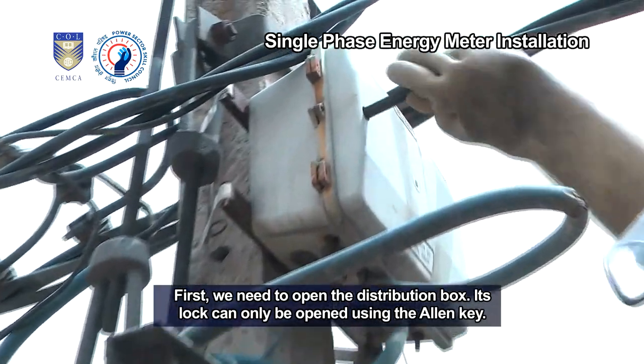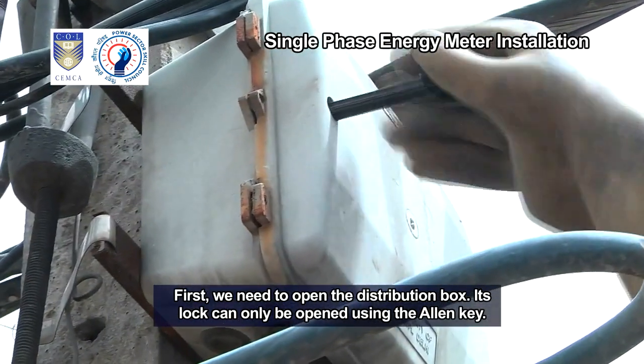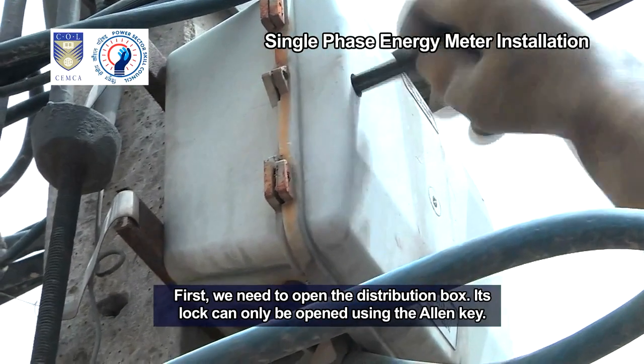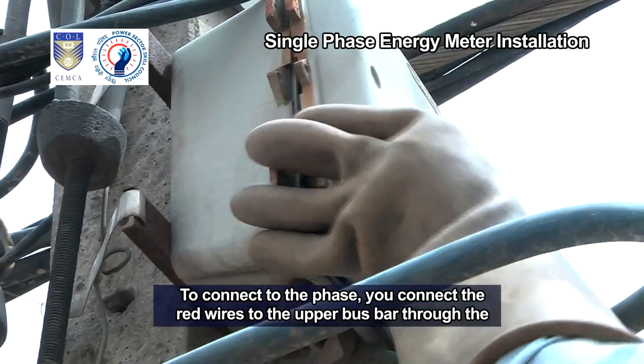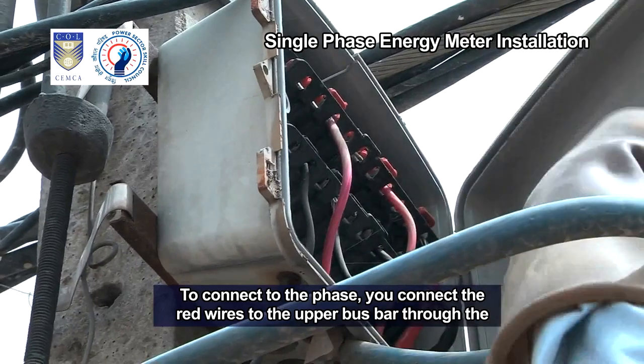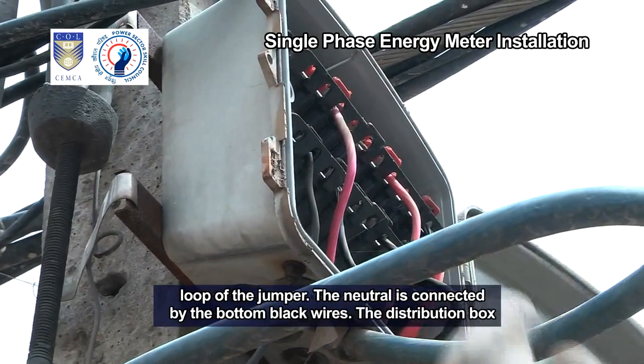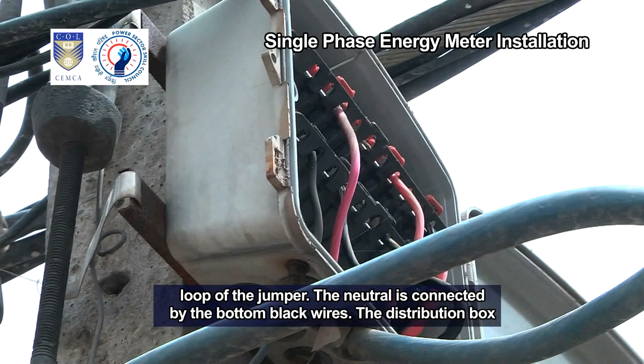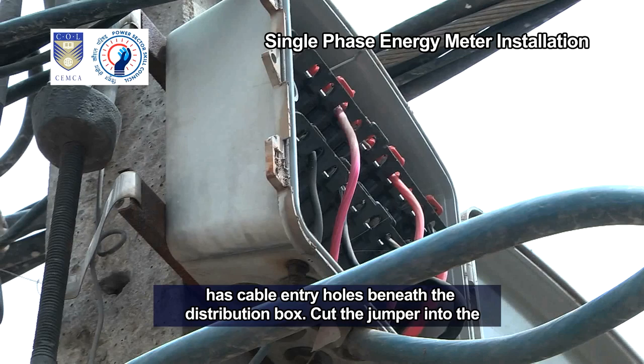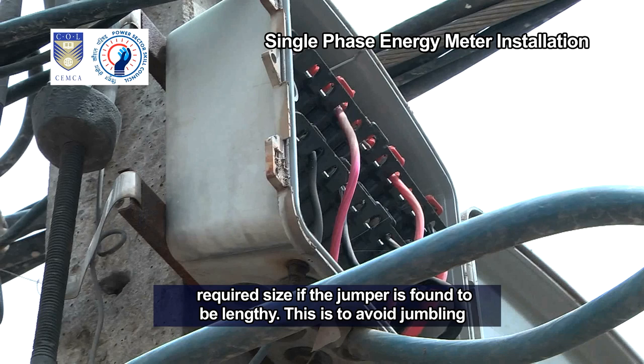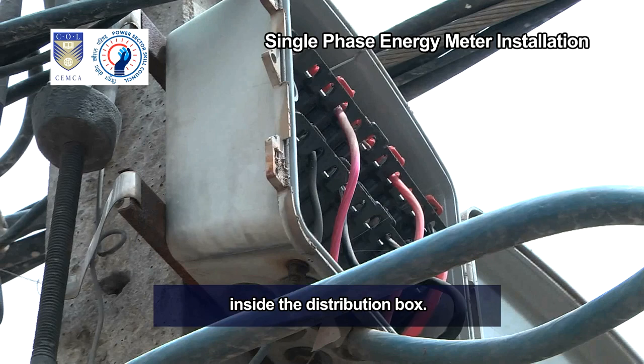First, we need to open the distribution box. Its lock can only be opened using the Allen key. To connect to the phase, you connect the red wires to the upper bus bar through the loop of the jumper. The neutral is connected by the bottom black wires. The distribution box has cable entry holes beneath it. Cut the jumper to the required size if the jumper is found to be lengthy. This is to avoid jumbling inside the distribution box.